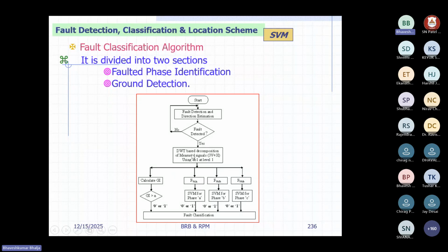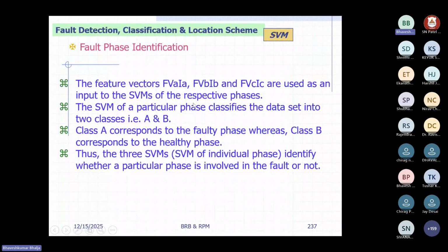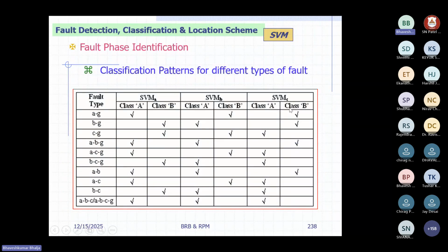And then we have suggested a fault classification algorithm. We have suggested faulty phase identification also, so that it can be used for auto reclosing purposes. Because if I want to, let's say, reclose the R pole of the breaker, then I must know in which phase the fault is there, which phase is faulty, whether R phase, Y phase, or B phase. So this will also tell which phase is faulty. And the faulty phase alone is not sufficient. You also have to see whether the fault involves ground or not. So this is also covered here. And then faulty phase identification is to be done using three SVMs: A phase, B phase, and C phase. And different types of faults we have considered, and we have classified each fault, right? That is there.